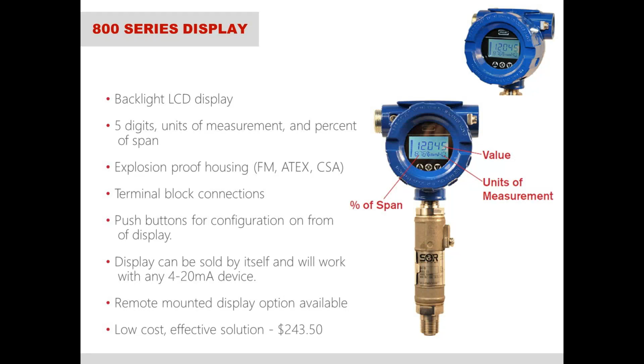So the display itself does not actually talk to the transmitter. All it does is it is in loop with the 4 to 20 milliamp signal and assigns a value for a 4 milliamp and assigns a value for a 20 milliamp signal. And then it linearly interpolates in between there. And so if you need to change your pressure reading, you will change the transmitter and then you also change the display as well.